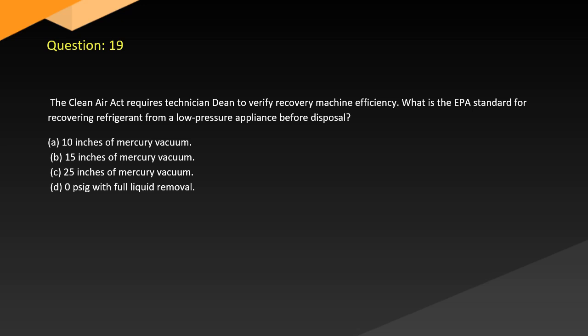Question 19. The Clean Air Act requires technician Dean to verify recovery machine efficiency. What is the EPA standard for recovering refrigerant from a low-pressure appliance before disposal? A. 10 inches of mercury vacuum. B. 15 inches of mercury vacuum. C. 25 inches of mercury vacuum. D. 0 psig with full liquid removal.